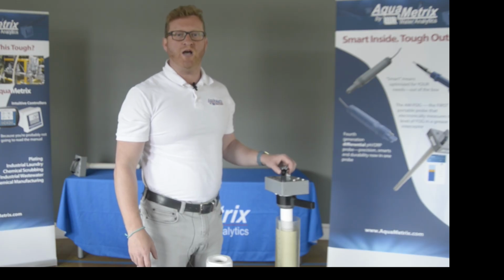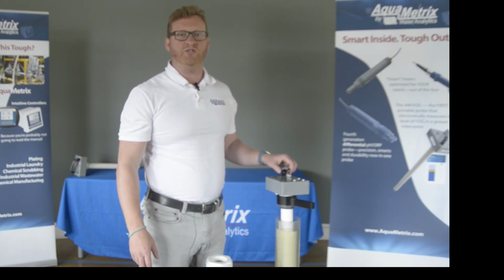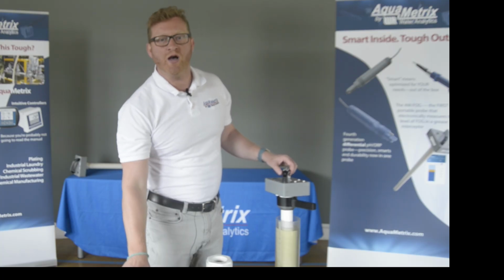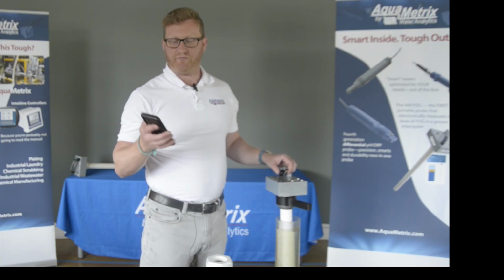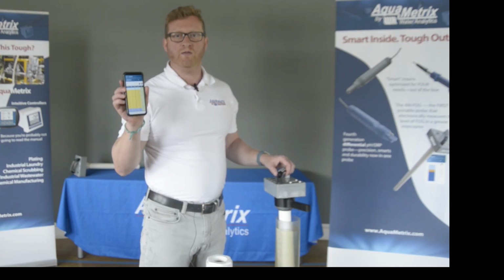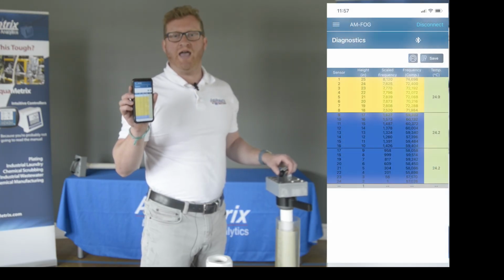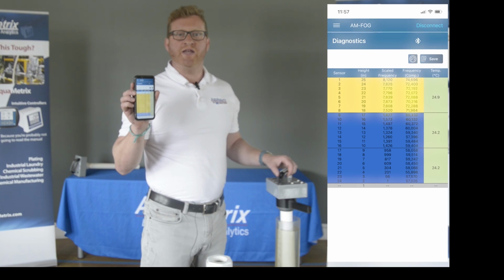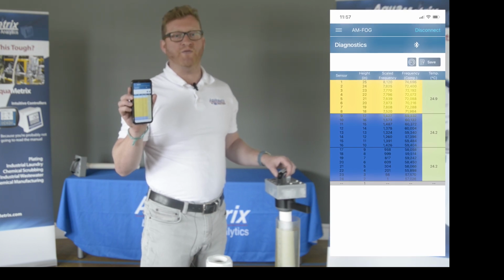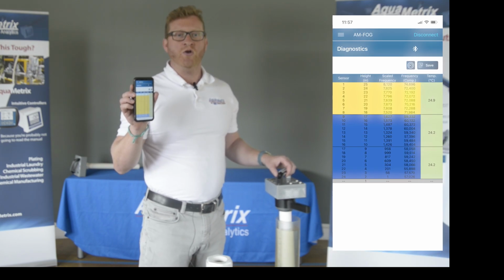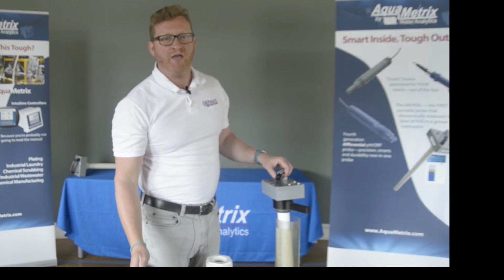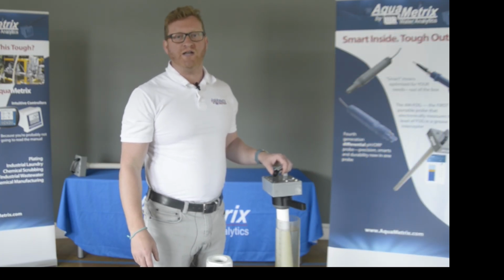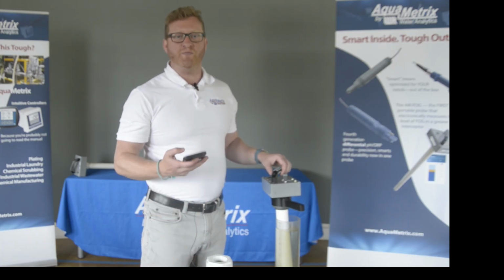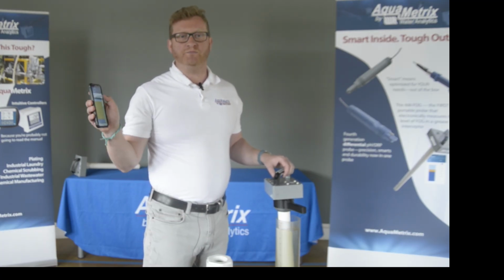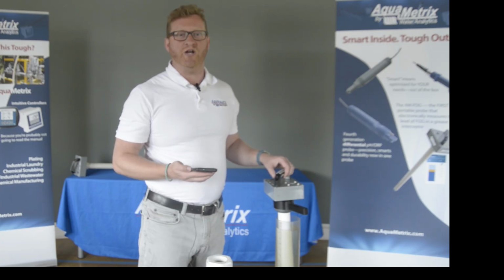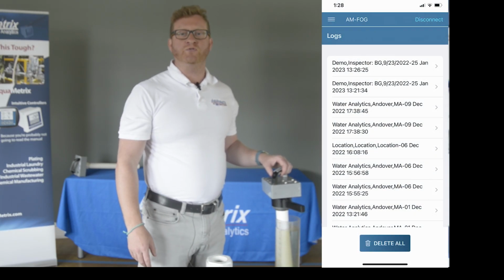Because the probe knows where the top of the water level is, the app calculates the percentage of fog in the interceptor. To really see what's going on, just go to the diagnostic screen. You can see the actual measurements at every inch in addition to the temperature of the inside of the trap. That's very useful information for fine-tuning the set points in the setup screen. We'll go more into that in the next video. If you're an inspector or hauler and you're visiting several restaurants, then you'll want to save the measurements you just made. Just simply hit the Save button. And the app saves the diagnostic screenshots along with the name and location of the food service establishment.